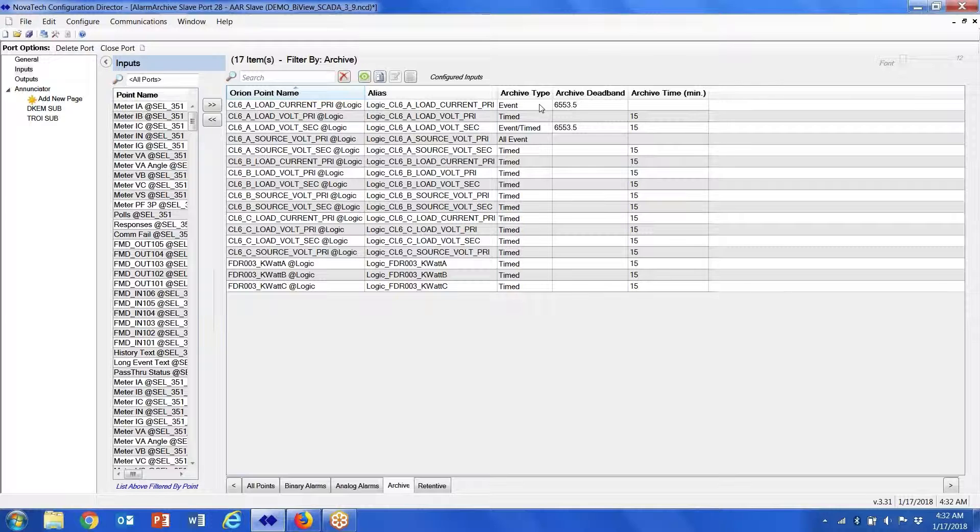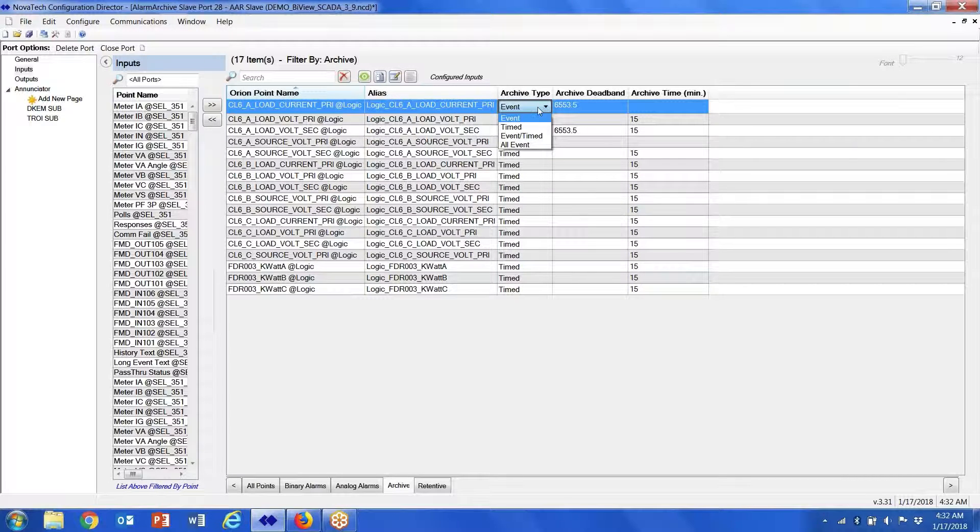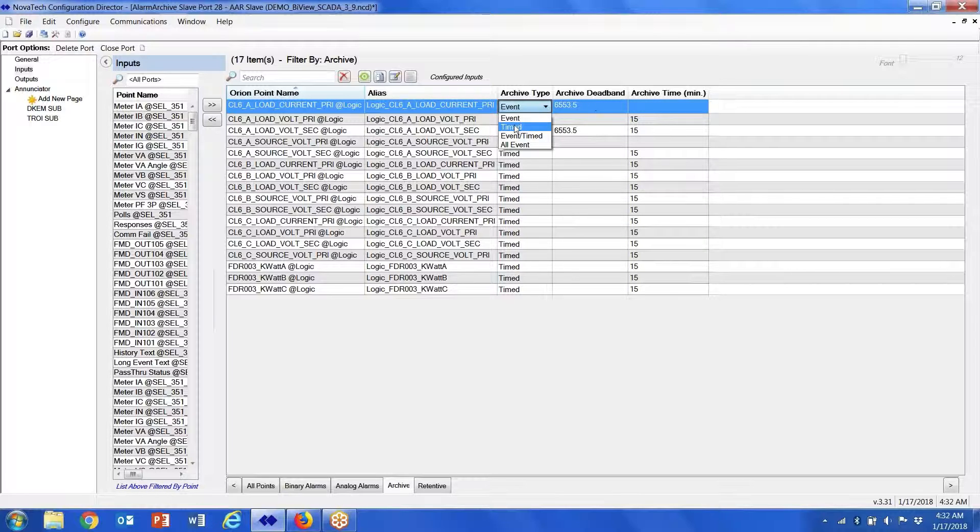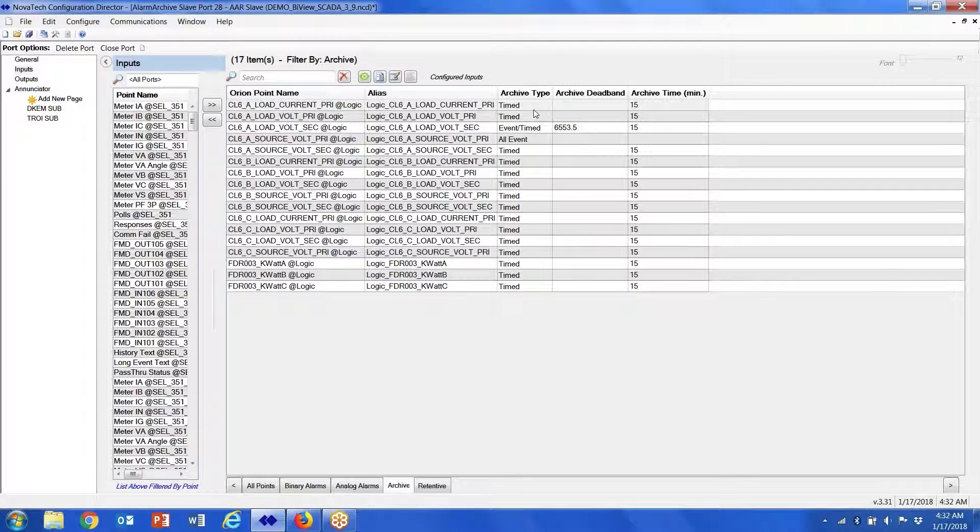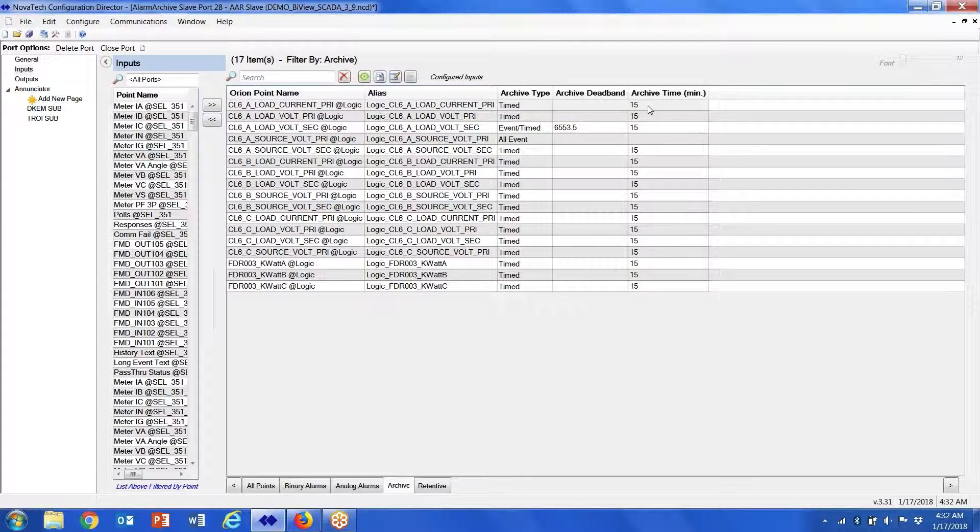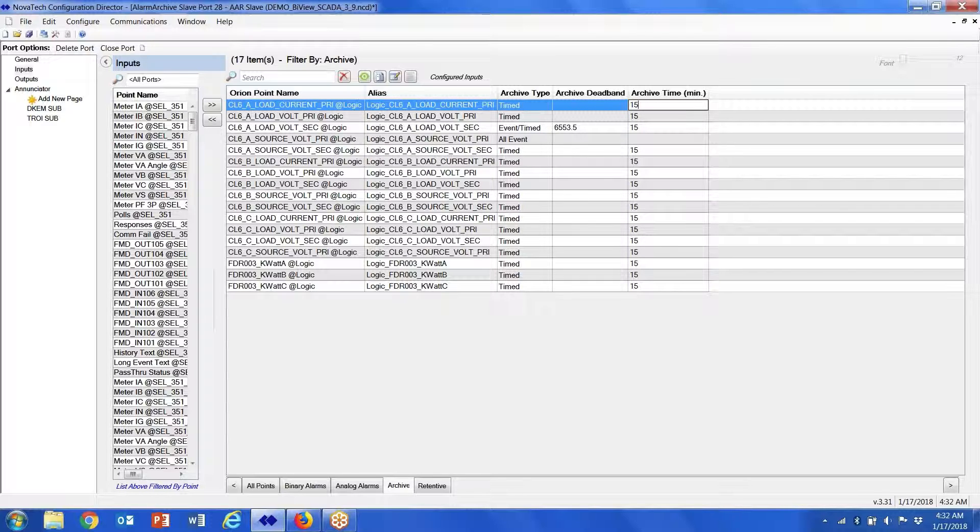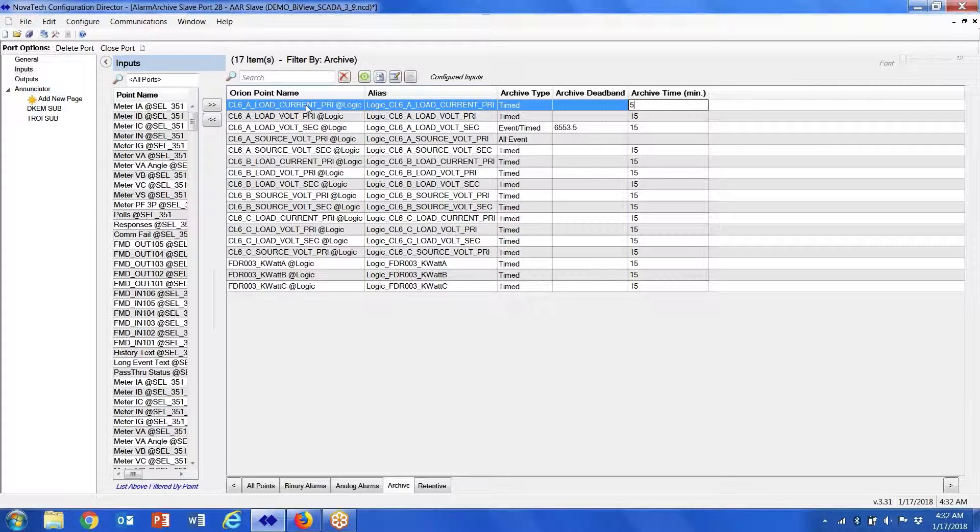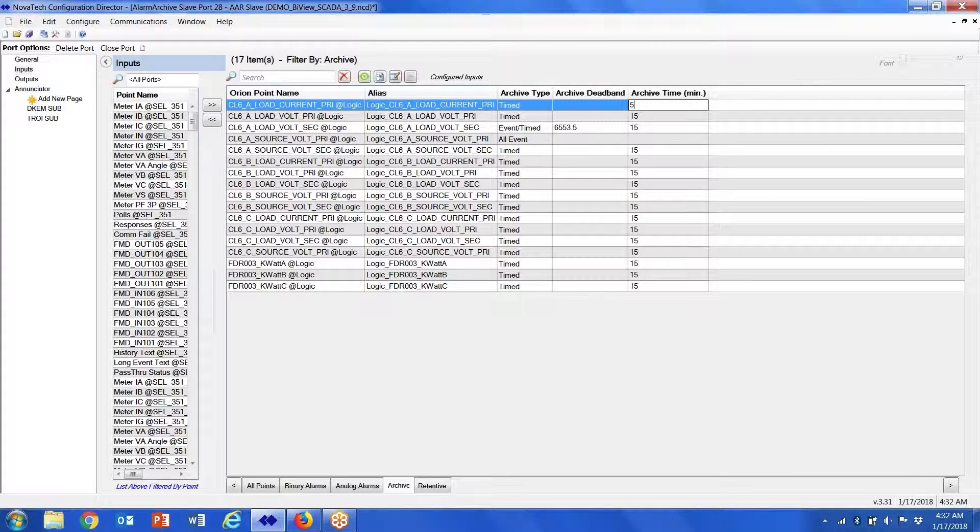There's a couple of drop-down menus. We can archive them based on events, which is a change in deadband. We can archive them based on time—so every 15 minutes, every minute, every five minutes, etc. So that point that's in the database is going to get archived in the PostgreSQL database every five minutes.